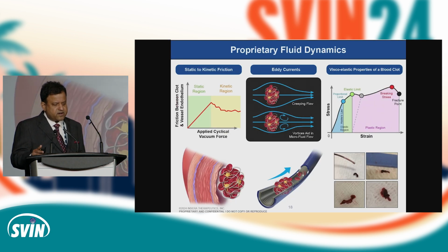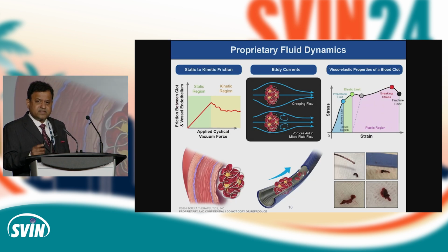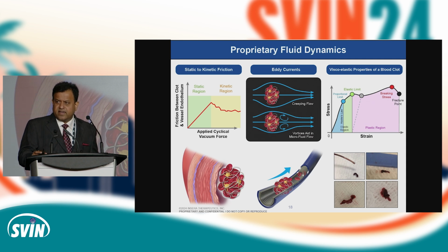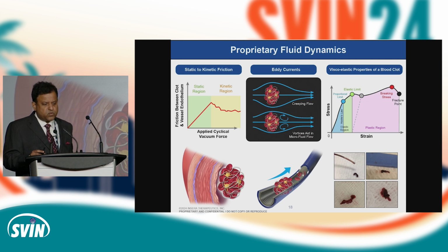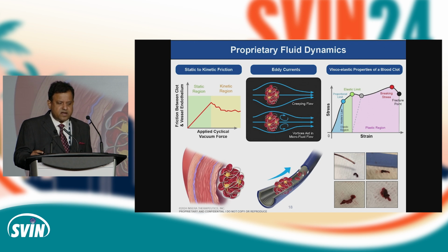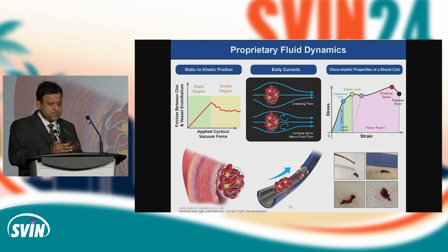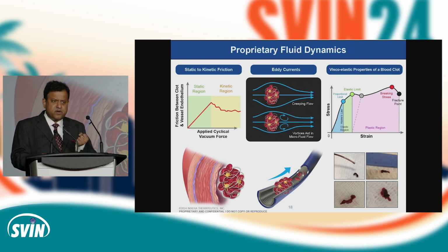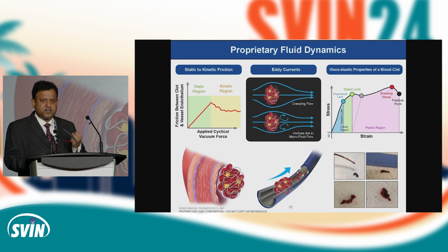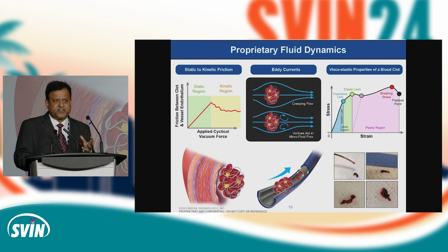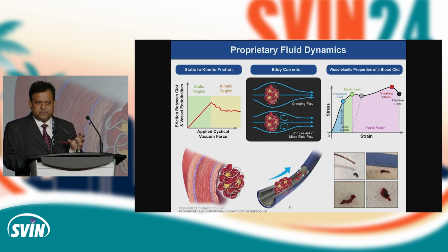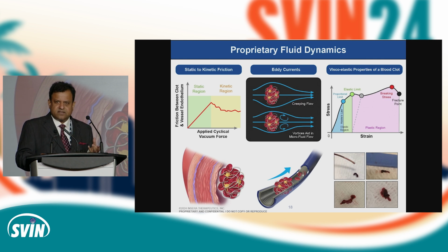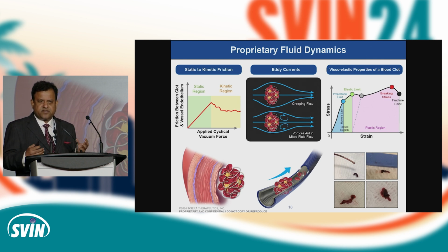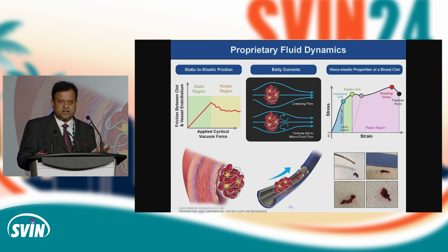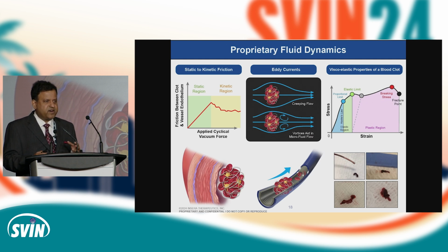The proprietary fluid dynamics at the core of this, you can look at as a triad, and it depends on which type of clot you're dealing with. One of the three vertices of this triad comes into play. The first one is static friction when the clot is adherent to the wall. To pull this clot out, your suction force has to overcome the static friction, the stickiness of the clot to the endothelium. What we achieve with cyclical aspiration is that by stretching and relaxing the clot, you're converting that static friction to kinetic friction, which is easier to overcome.